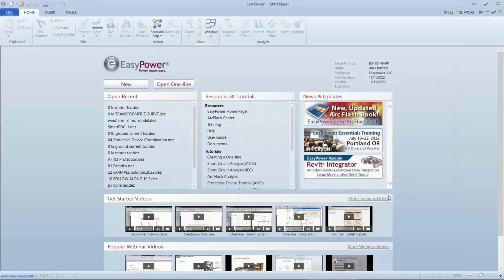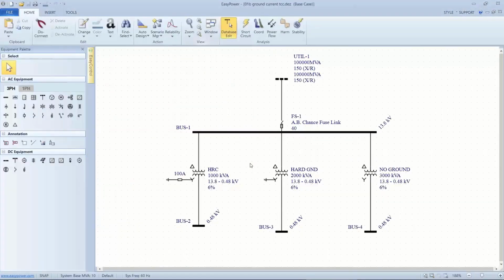So what we're talking about is single line to ground and ground protection, and the fact that we have to consider this 58% lower rating when we're monitoring primary current. So here we have three situations: high resistance ground, as indicated by this resistor in the neutral connection on the Y side; here we have a hard ground; and here we have a delta Y with no ground.